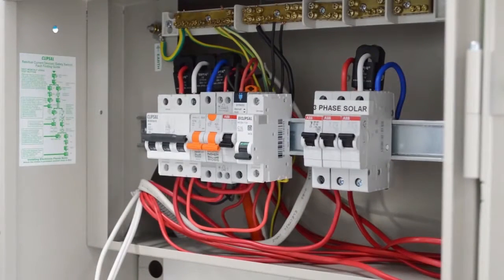It's important to note now that if switching air conditioning, it is very important to ensure that the air conditioning unit does not fall back onto a standby setting when switched off and on again at a circuit level. You must always check the function of an air conditioning unit before switching. The owner must be home for this to take place. Once a suitable circuit has been identified and the owner agrees to have it switched, you can proceed.